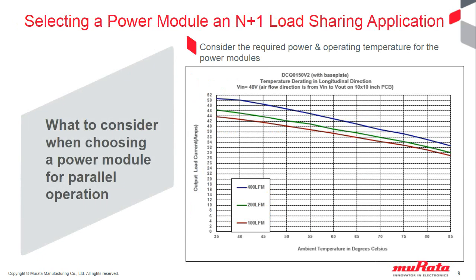So you need to consider the required power and operating temperature range for the modules. As we discussed earlier, with two modules sharing a 600-watt load, you'd think that you only need 300-watt capability from each module. Well, that's not true in an N+1 situation, because if one module fails, the other module has to keep the system up and running. So you need a 600-watt power module. Temperature is an important factor. As you can see here, the brown line is at 55 degrees C. You follow the 55-degree line up to where it crosses, and you can see that the module is capable of 450 watts with 100 linear feet per minute airflow.